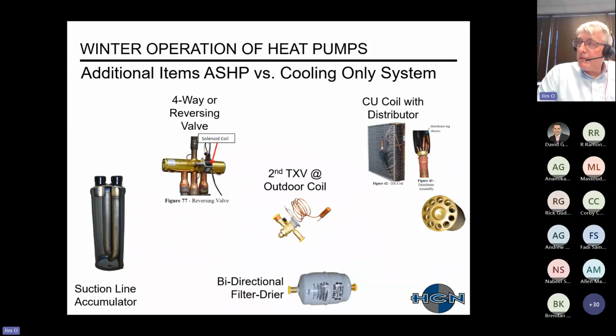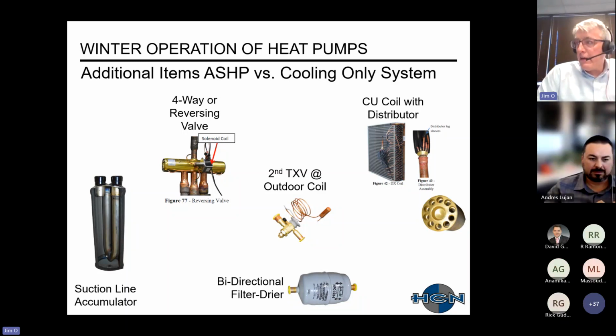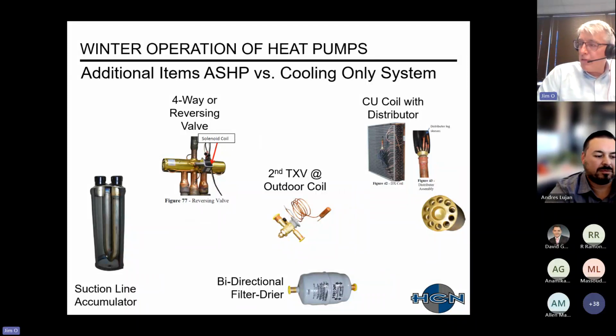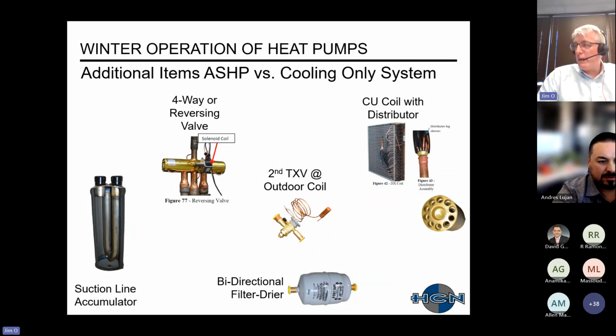Just a quick review of the additional items that are used with a heat pump versus a cooling-only system. From left to right, we have a suction line accumulator. We have a 4-way reversing valve. On our outdoor coil, we have a second thermal expansion valve, and along with that thermal expansion valve, we have a distributor cap as well as the spider piping. And then our filter dryer goes from a single flow to a dual or bidirectional flow filter dryer.